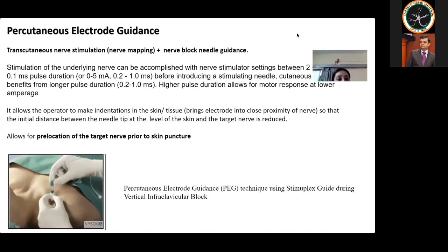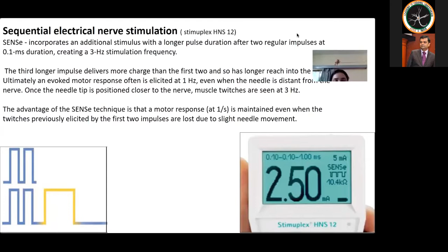Then we have the sequential electrical nerve stimulation. It incorporates an additional stimulus of longer pulse duration after two regular impulses at 0.1 millisecond. We get a 3 hertz stimulation frequency. Here, as you can see in the picture, the third longer impulse will deliver more charge than the first two, and this will help reach the nerve faster. So ultimately, an evoked motor response is often elicited at 1 hertz even when the needle is distant from the nerve. Once the needle is positioned closer to the nerve, the muscle twitches are seen at 3 hertz.